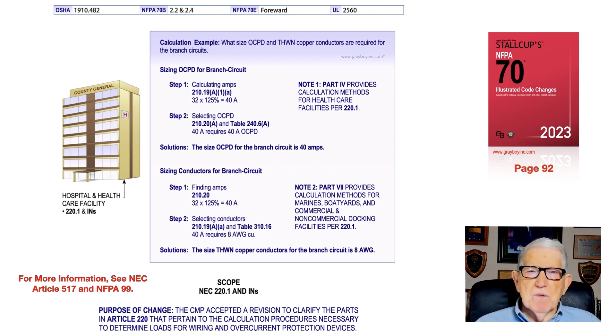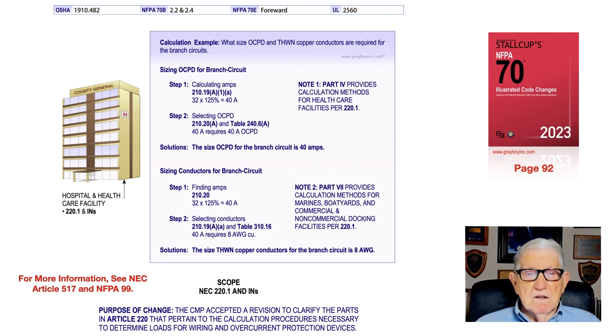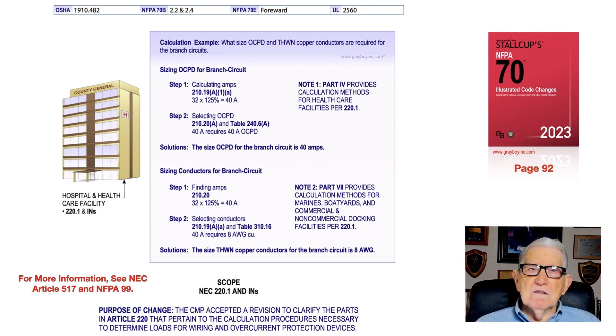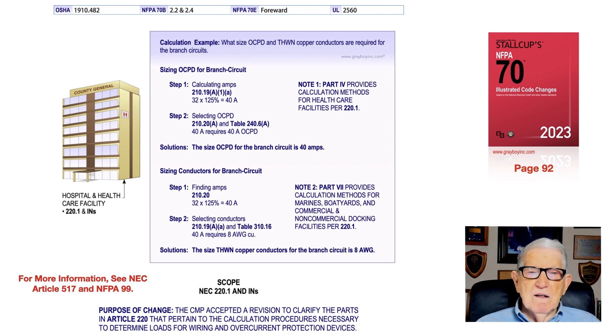Sizing the branch circuits, we go through the same procedure. We take 125 percent of 32 amps, we come up with 40 amps, and then the 40 amps would require us, per 210.19(a)(1), to select from table 310.16 a number 8 conductor based upon that 40-amp calculation. Part 4 note 1 defines calculation methods for health care facilities, and note 2 picks up Part 7, which provides calculation methods for marinas, boat yards, and commercial and non-commercial docking facilities per 220.1.